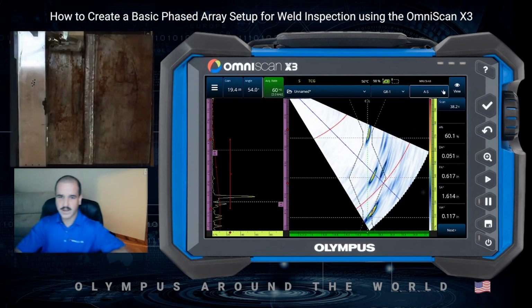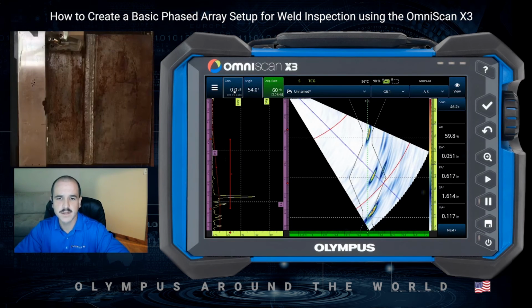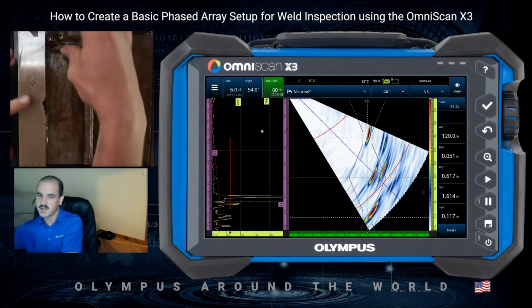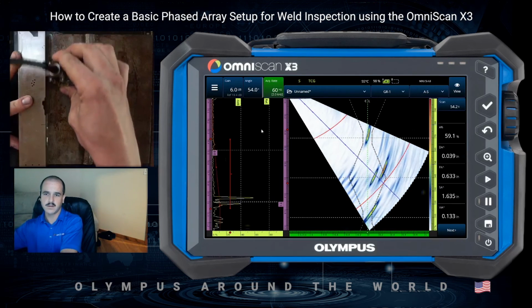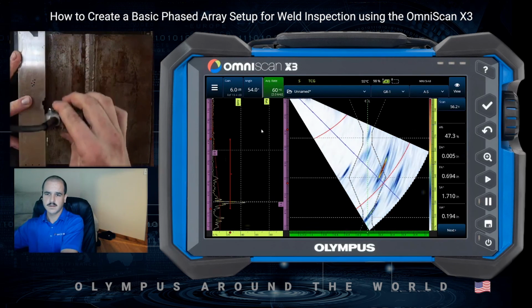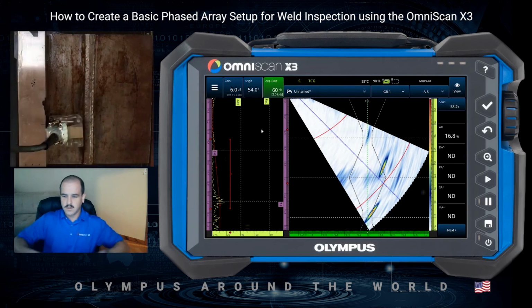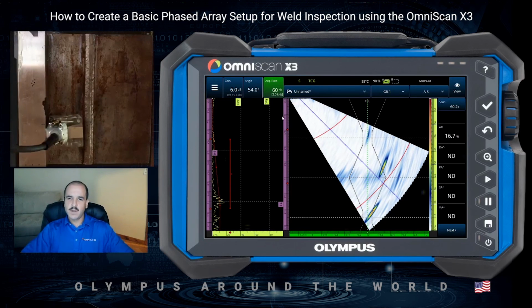And that's about it. So the only next step you can do if you want to add a bit of scanning gain, we can long press on our A scan here, enable our reference, come to our gain tab here. I'm just going to adjust this to 6 dB, and there we can add 6 dB of scanning gain. So that's it for a basic phased array weld inspection setup, single-sided, non-encoded.